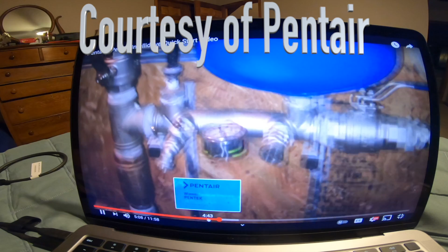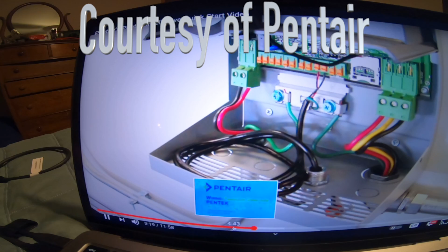Also, after installing the transducer and running the cable to the Pentek Intellidrive, make sure that any extra transducer cable is cut and removed, never coiled on the outside or inside of the Pentek Intellidrive housing, as this could result in RFI interference, which can damage the drive. When wires are being run, you want to make sure that you don't cross your wires with each other, and if they can't be avoided, make sure you cross them at a right angle. This transducer is supposed to be at least a foot away from any connection and after the tank. It looks like it's before the tank, if you ask me.